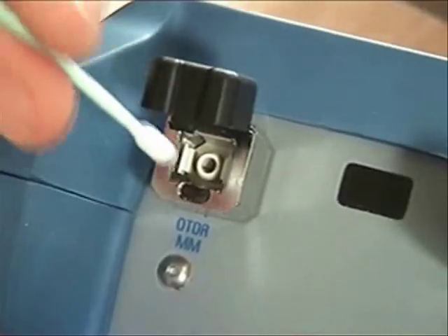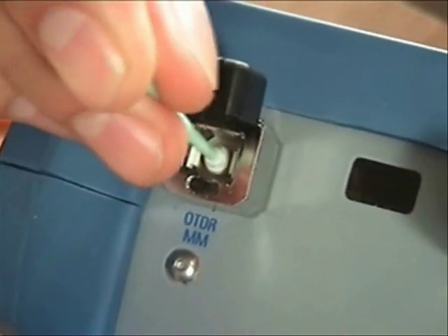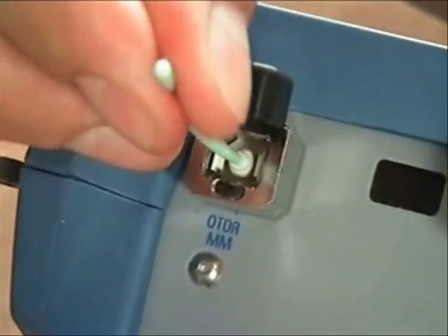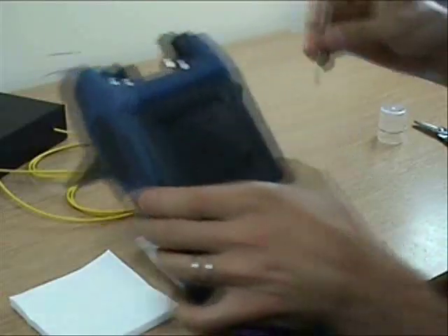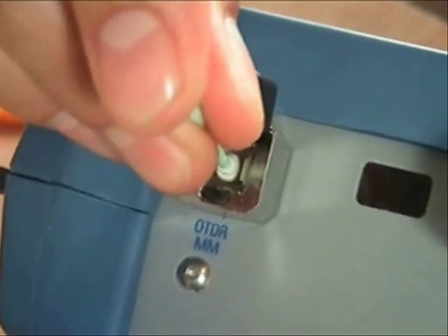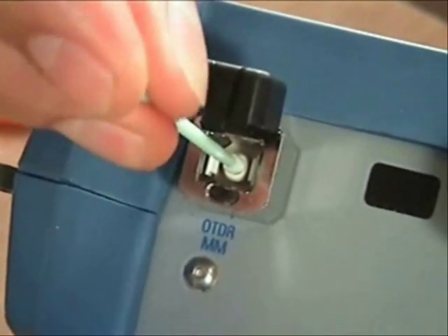Insert the bud into the multi-mode OTDR port, twisting two or three times to help loosen the dirt. Repeat this process with the dry bud to ensure the port is completely clean and free of dirt.